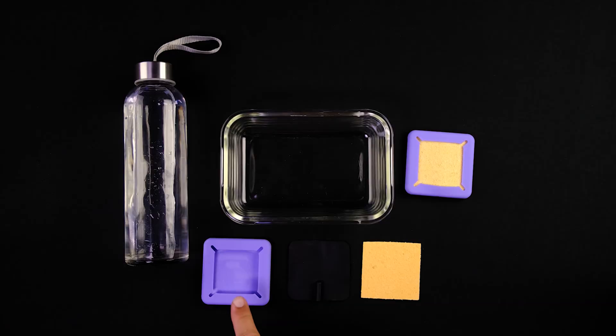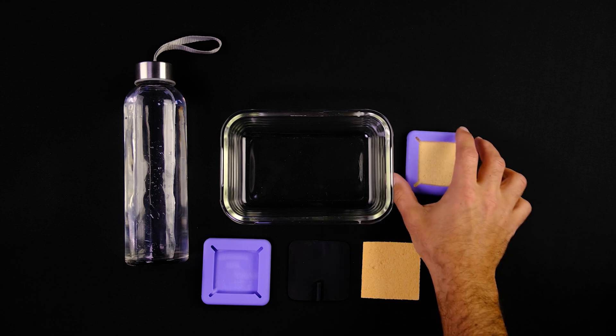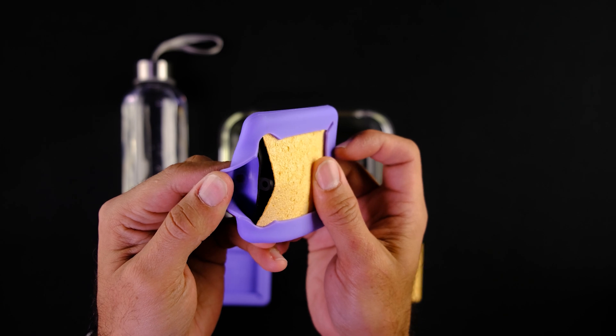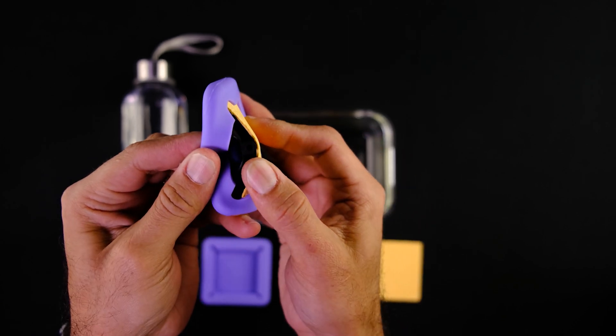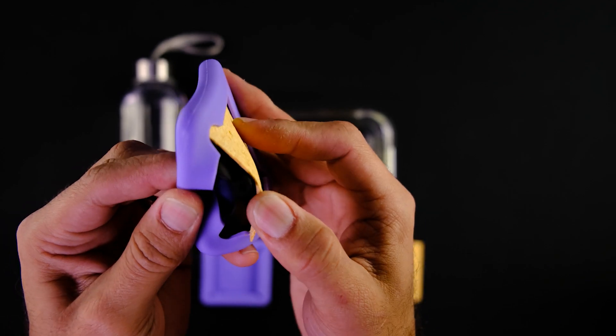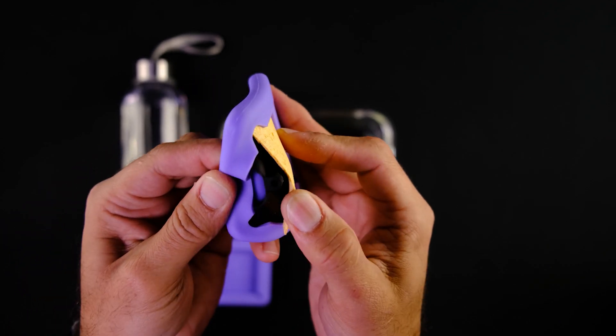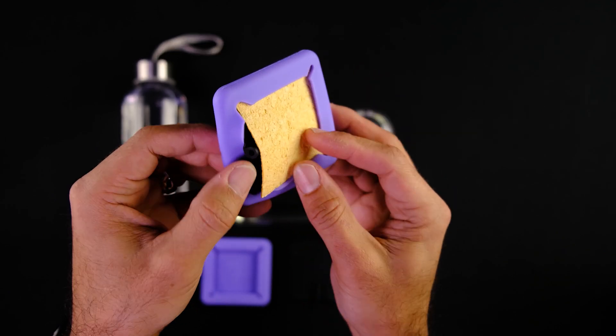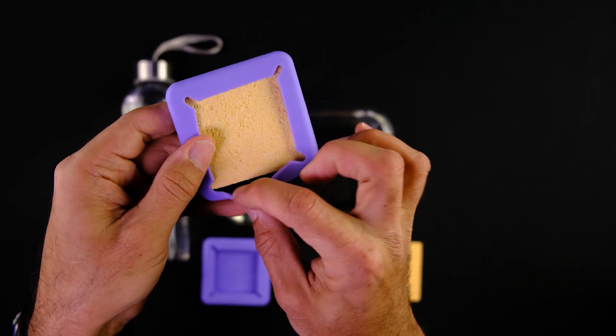The electrosquare components consist of three parts: the outer silicone shell, an inner conductive pad, and a layer of cellulose sponge. The shell and sponge are insulators. The carbon pad is the only part that naturally conducts electricity. When saline is added, electrical current flows from the conductive pad through the sponge via the saline solution. That in a nutshell is how the electrosquare electrodes work.